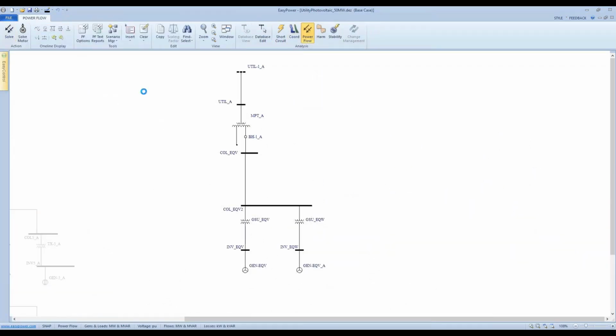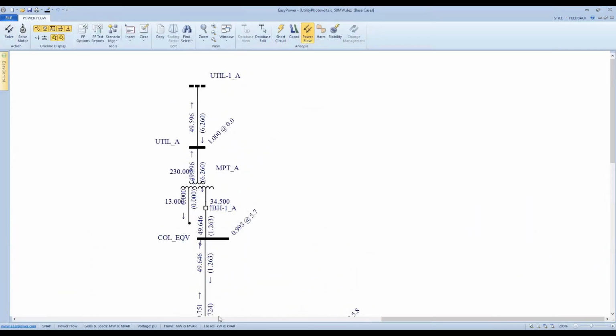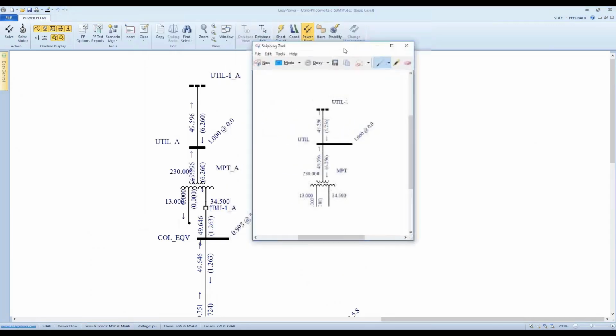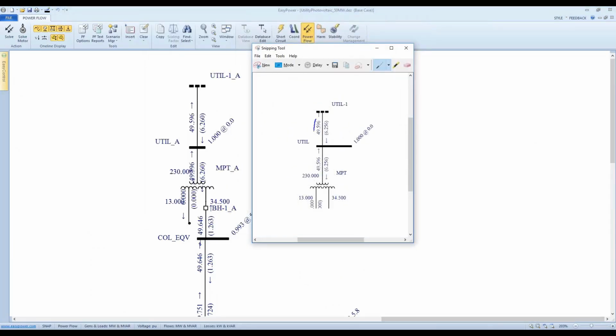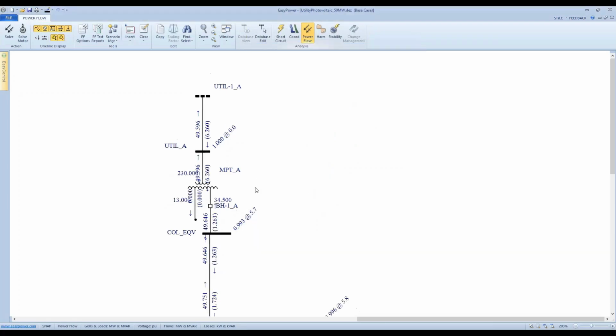So solve the power flow, compare. 49.596, exactly the same. Reactive power 6.256, 6.260, close enough, less than 1%, 0.1% actually. So, okay, this is the right model we should be using.